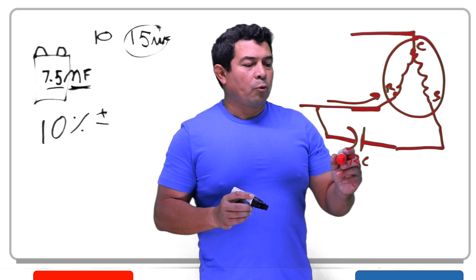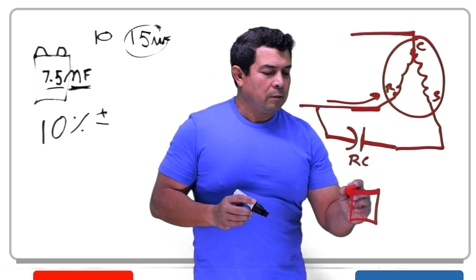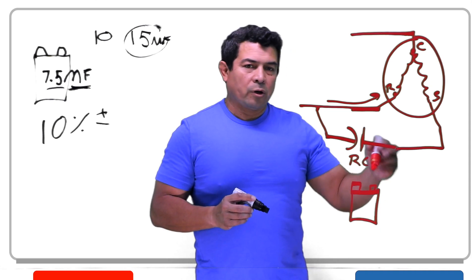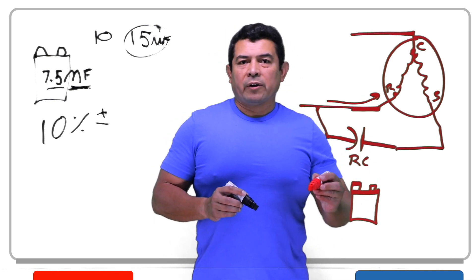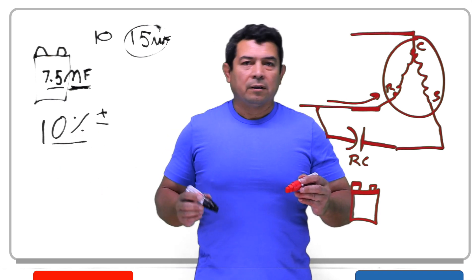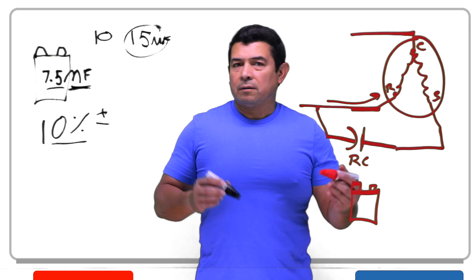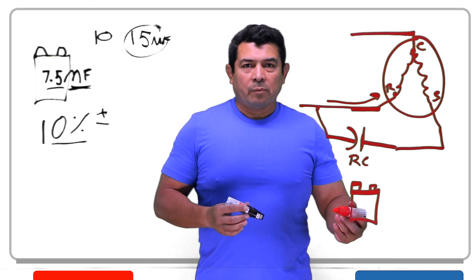So this capacitor, what we're going to do is we're going to take it off of here, and we're going to hook up the meter to it to see what the microfarads are. If they are within 10%, then we're okay. We know the capacitor is good. If they're not, then we know the capacitor is bad.